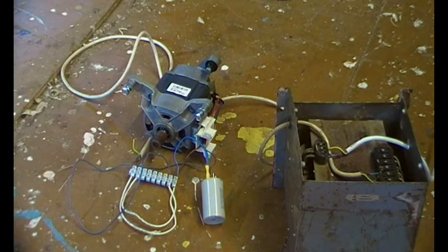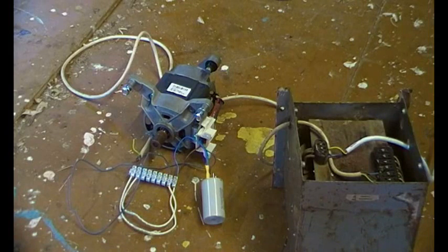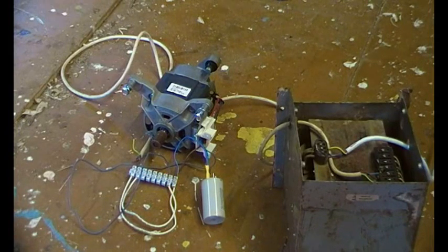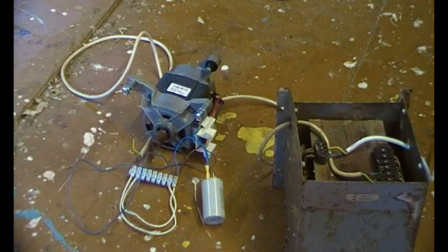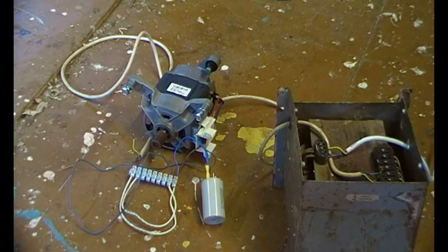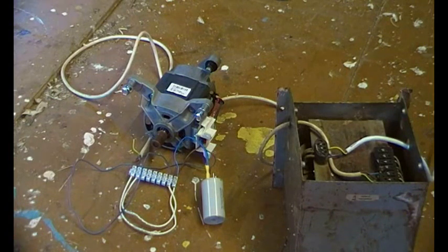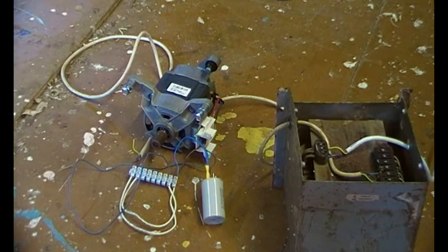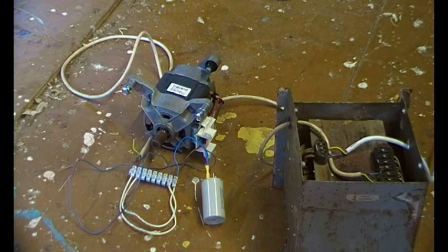Right, they don't want to know, so the capacitor's not big enough now. Let's just change that. Okay, there's a bigger capacitor. There we go, it will work on 110 quite happily. And that's a 16 microfarad capacitor. And it will be 2800 revs because it's on 50 cycles.